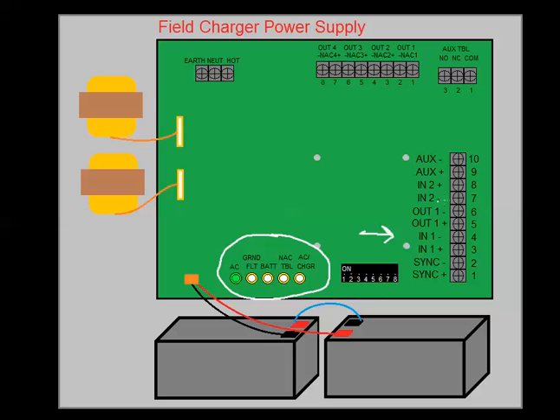And any time this goes into trouble, there are contacts between terminal 3 down here and terminal 5, which is the input positive and the output positive, which are connected until this goes into trouble. When this goes into trouble, these two terminals, which are internally connected, that opens up. Those would no longer be connected if there was a trouble. And also this is important if this is not in alarm. So in a standby state, when the input is not triggered and being told that it's on, terminals 5 and 3 are connected when the panel's secure, meaning there's no faults on any of the wiring, the output wiring, no shorts, no ground faults, etc.